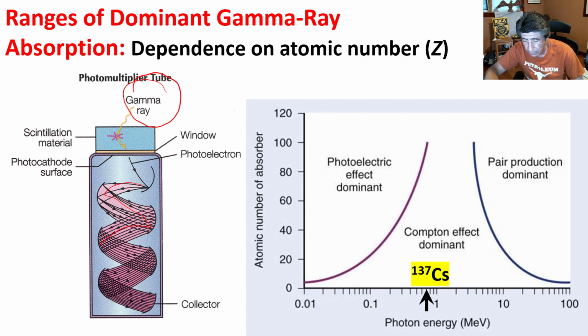So we have the scintillator and the photomultiplier, and essentially the energy of the gamma ray as it impacts the scintillator will be recorded as a voltage, and the higher the voltage, the higher the energy. So we have a way to distinguish between the different energies of the gamma rays as they come, and potentially we can differentiate the low energies from the high energies by way of several energy windows.